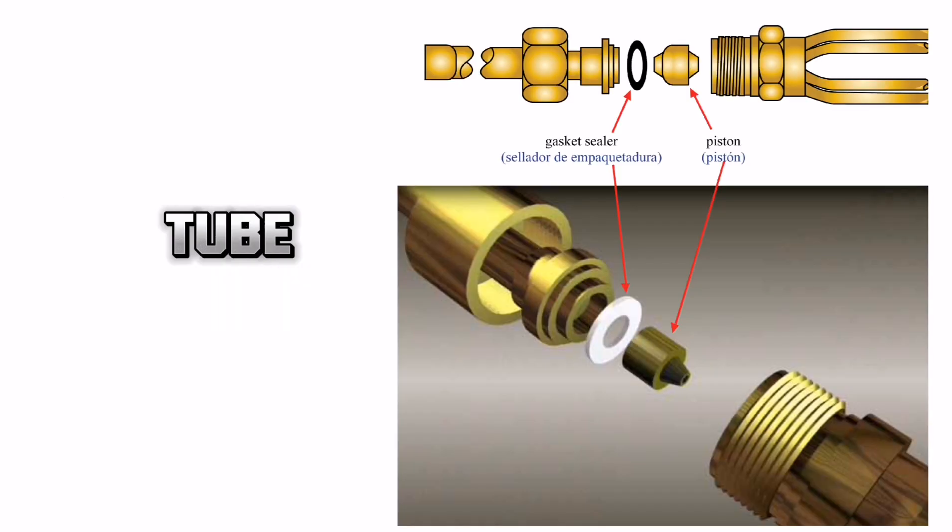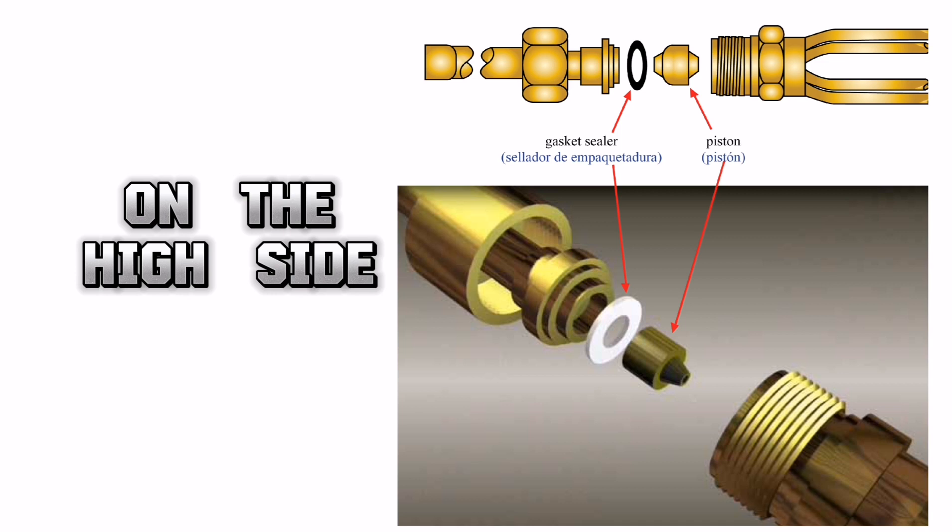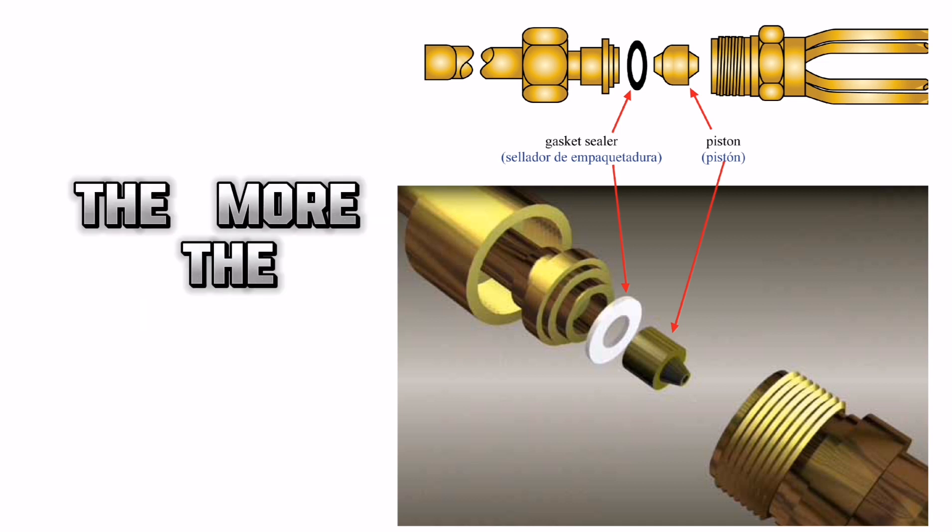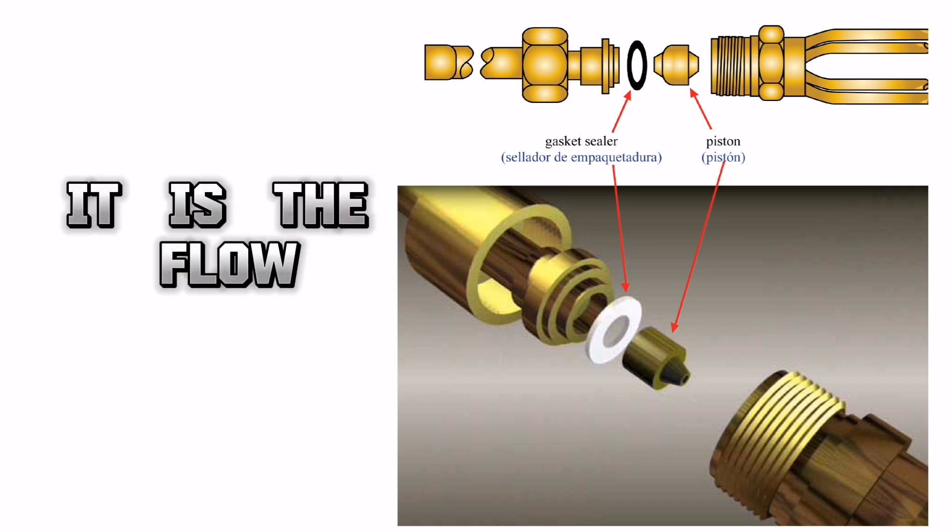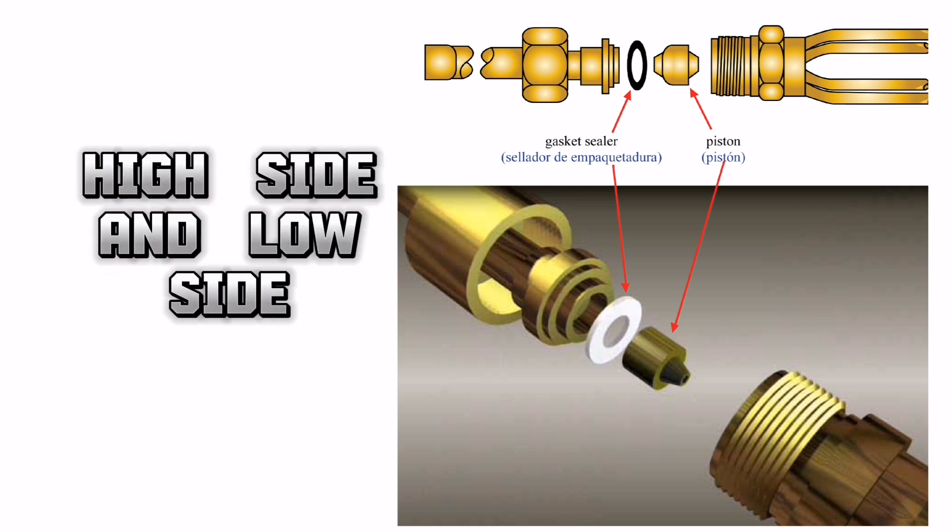Just like the capillary tube, the higher the pressure on the high side, the more flow you're going to have. The higher the pressure in the evaporator, the less flow you're going to have. It is the flow that these two are going to be maintaining. Again, they used to use the high side and the low side float, but they've gotten away from those.